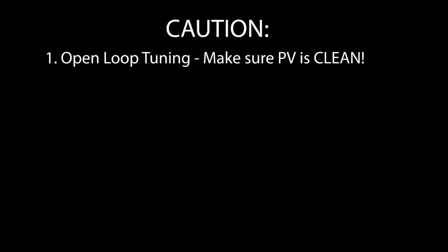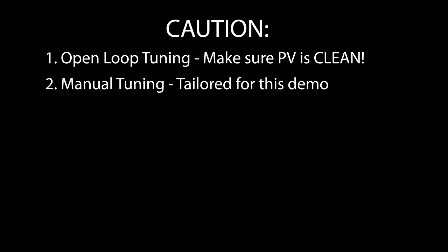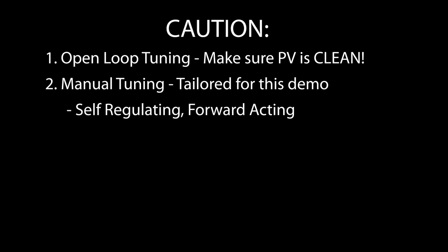A couple of things you need to be aware of. This Open Loop Auto-Tune was done with some pretty heavy filtering on the process variable. Open Loop Auto-Tune is even more sensitive to noise than closed loop, so make sure you have a good, clean process variable before doing an Open Loop Auto-Tune.